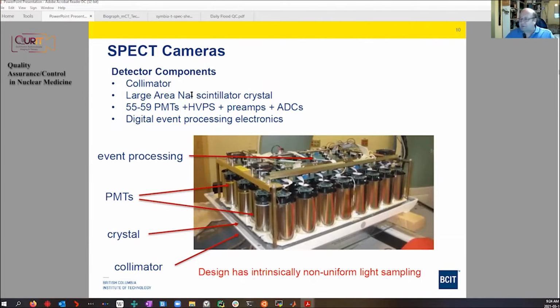So I believe you've learned about SPECT cameras. The main parts are the detectors. The detectors consist of a collimator. The collimator is essentially the lens of the camera. If you take the collimator off, you don't get an image. Then you have a large area sodium iodide scintillation crystal. Then you have a set of 55 to 59 photomultiplier tubes. That's what you see here in the tin cans. The tin cans are actually mu-metal magnetic shielding. Each of these is a photomultiplier tube. It detects the scintillator light. These are connected to high voltage power supplies, preamps, and then the signals are digitized in ADCs. The signals go into digital processing electronics, which, by comparing the digitized signals from the PMTs, calculate the location where the gamma ray hit the scintillator. That location is called the address.